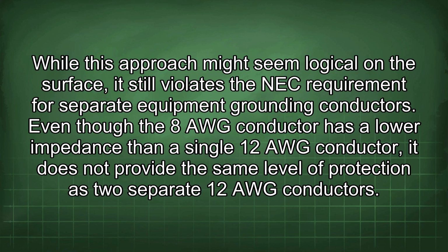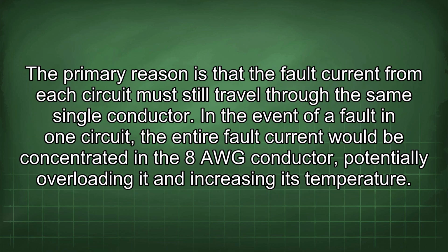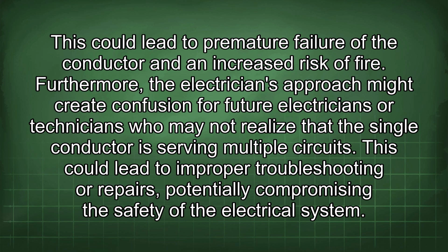Even though the 8 AWG conductor has a lower impedance than a single 12 AWG conductor, it does not provide the same level of protection as two separate 12 AWG conductors. The primary reason is that the fault current from each circuit must still travel through the same single conductor. In the event of a fault in one circuit, the entire fault current would be concentrated in the 8 AWG conductor, potentially overloading it and increasing its temperature. This could lead to premature failure of the conductor and an increased risk of fire.